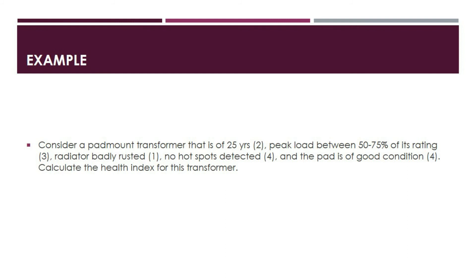Now let us go over an example. Consider a pad mount transformer that is 25 years of age, so the rating will be 2 in that category. The peak load is between 50 to 75% of its rating, so we give a rating of 3 in that category. The radiator is badly rusted, so it is a rating of 1 in that category. The IR test reveals no hotspots are detected, so the highest rating of 4 is assigned. And the pad is in good condition, so again, 4. Calculate the health index for this transformer.